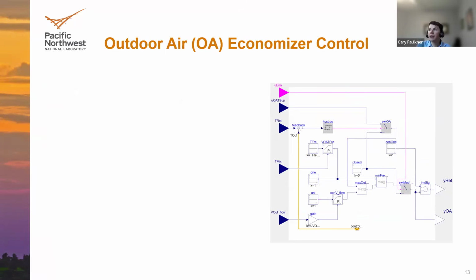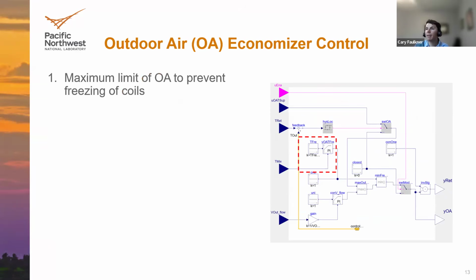And now let's talk a little bit about the outdoor air economizer control for these systems. So this is going to connect with how much outdoor airflow is going to be brought into these VAV systems, and it's applied to the zones downstream. There's three priorities for the outdoor air economizer. The first priority is to prevent freezing of the coils, because if the coils freeze due to bringing in too much cold outdoor air, then you're going to have major problems for your HVAC system and your building as a whole.